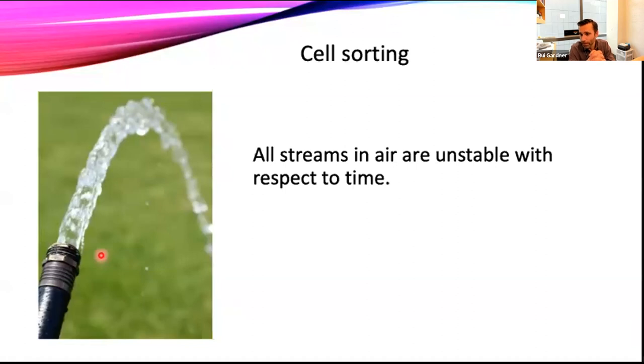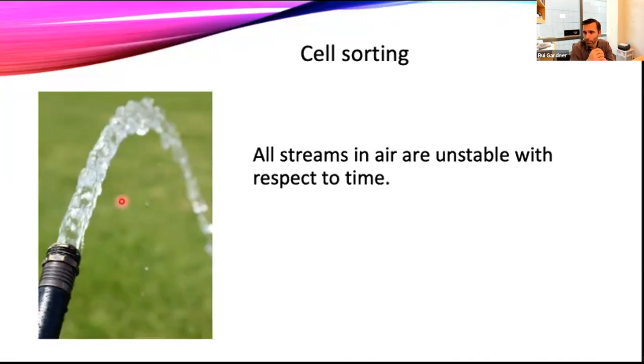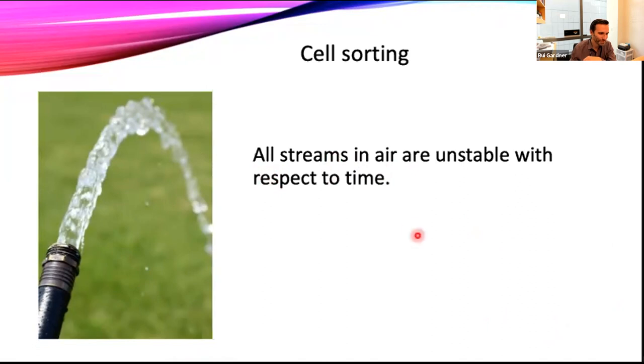The distance where droplets start to form depends on several things: the water pressure applied, the size of the orifice, the viscosity of the fluid, and the temperature. A question from the audience: do cells need to express fluorescence themselves or have something attached to the surface before sorting? We can sort cells on the basis of anything — an expressed fluorescent protein, a fluorescently labelled antibody on the surface of the cell, or even just the scatter properties of the cells. Virtually anything we can do on an analytical flow cytometer we can transfer across to the cell sorter, as long as we can differentiate somehow.